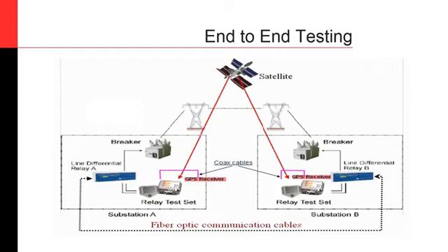It will reach one end of the line, I don't know, a few microseconds before the other end, and I have to account for that in my simulations. The only way I have to guarantee that there is an actual measurable moment to begin the test is to have a common time source.